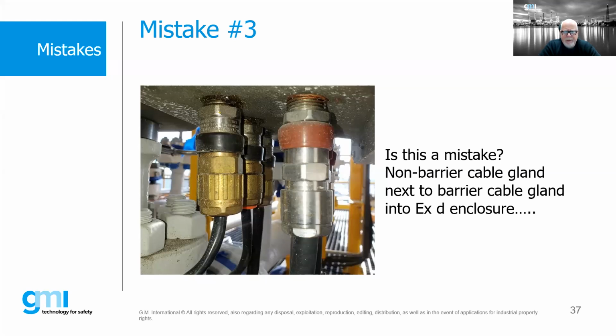Actually, as per the latest IEC 60079-14 standard, that may not be a mistake, because the requirement for selecting a barrier versus non-barrier EXD gland is based on cable length. As a rule of thumb, if we have very short lengths of cable going into flame-proof boxes, 3 meters or less, it requires a barrier gland. If the cable is 3 meters or longer, it does not necessarily require one.